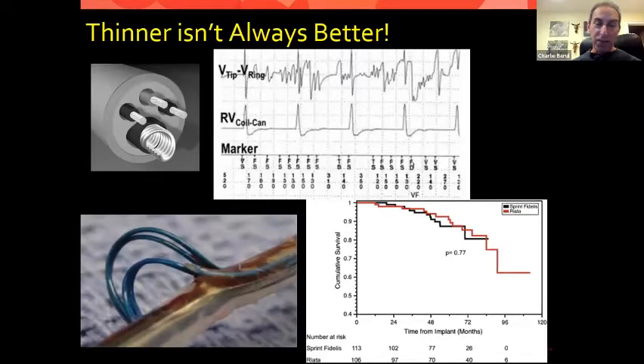And for those of you on this call that have defibrillators, if you've ever received a shock, it's great if it's a life-saving shock. It's not so great if it's an inappropriate shock if you're just sitting around doing nothing. And the other way to make the leads thinner, besides having less insulation between the conductors, is to have less insulation outside the conductors. And this is what happens here. You get extrusion of the conductors outside of the insulation. They break through, and those leads fail in a different way. And so both of these types of thin leads are now off the market because of a higher failure rate than the standard thickness leads.